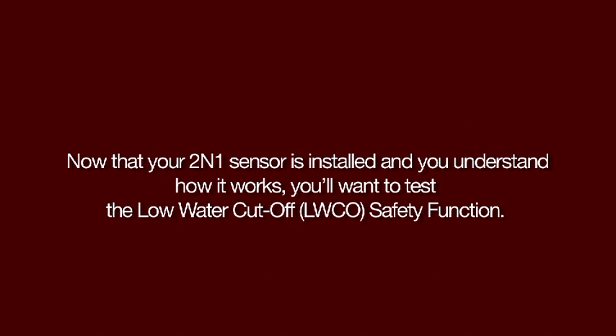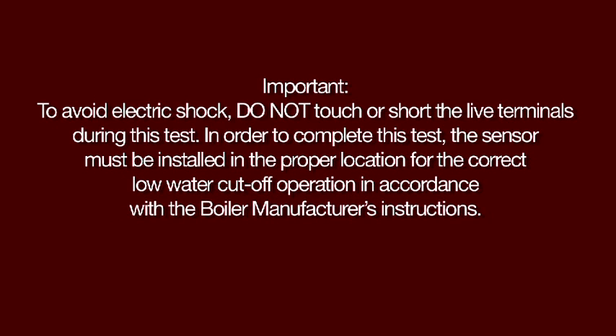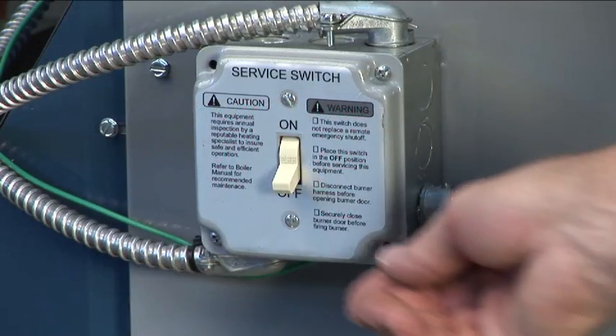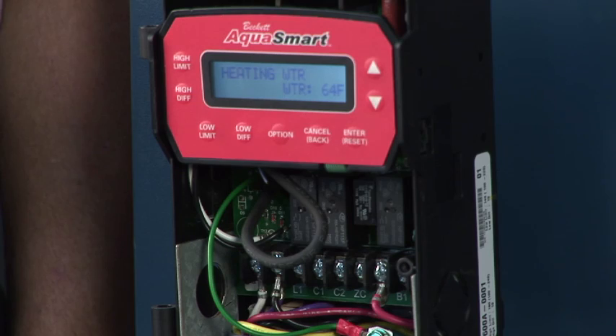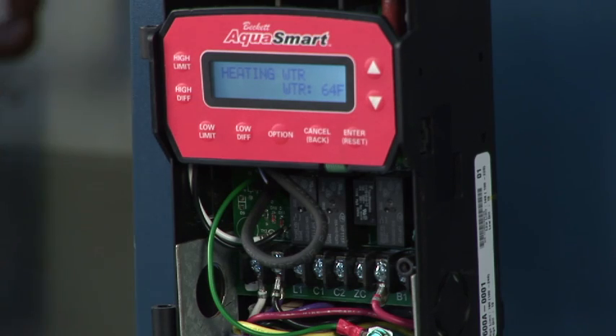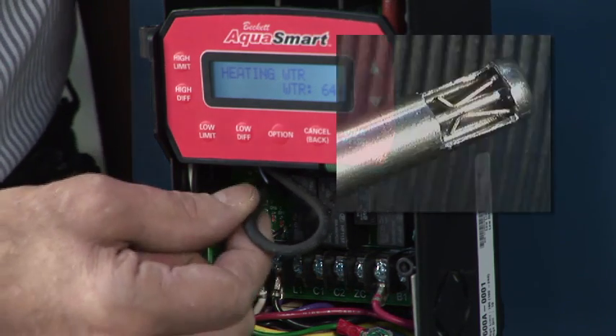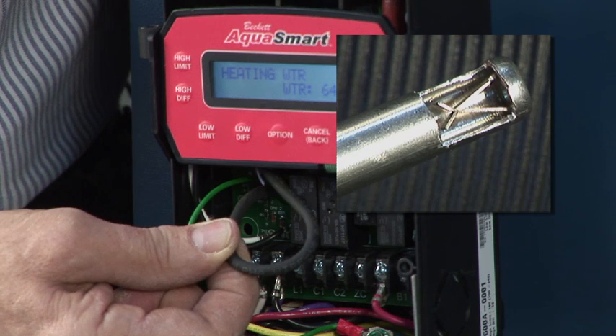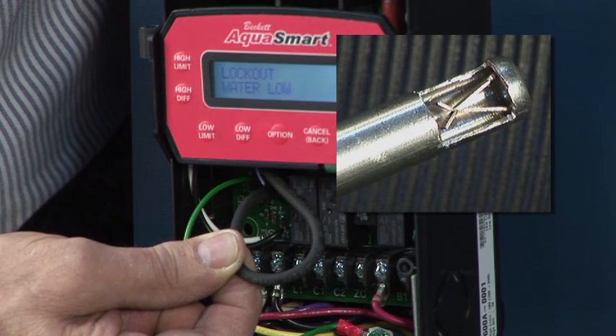Now that your 2N1 sensor is installed and you understand how it works, you'll want to test the low water cutoff LWCO safety function. Important: to avoid electric shock, do not touch or short the live terminals during this test. In order to complete this test, the sensor must be installed in the proper location for the correct low water cutoff operation in accordance with the boiler manufacturer's instructions. First, turn the electrical power on to energize the AquaSmart control. Next, pull the sensor probe partially out of the sensor thermowell to disengage the pin from the clip inside the tube. You'll be able to feel when the pin disengages.